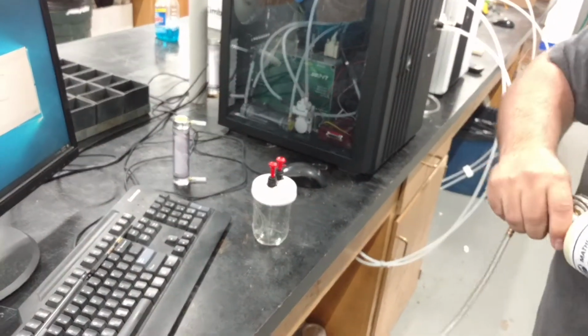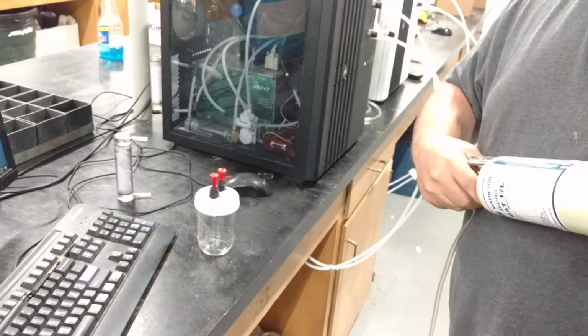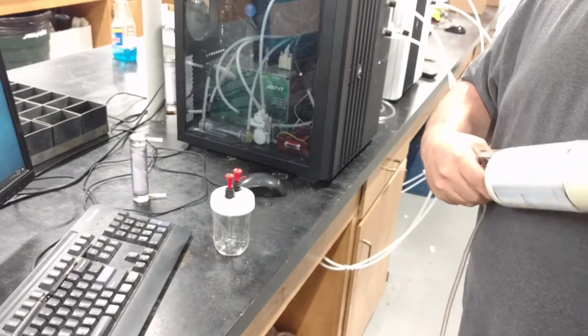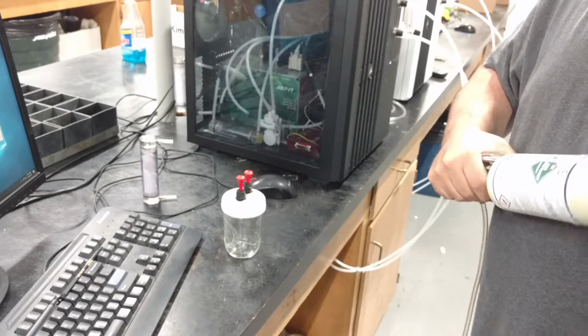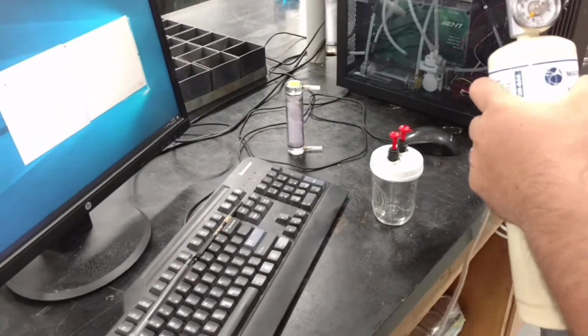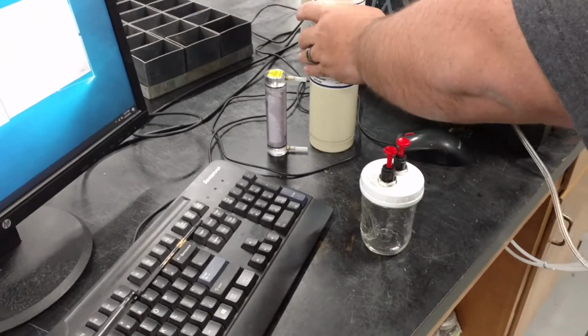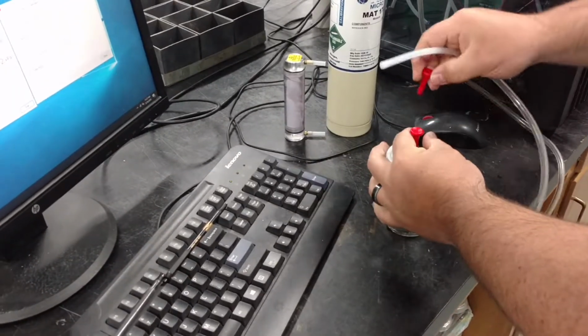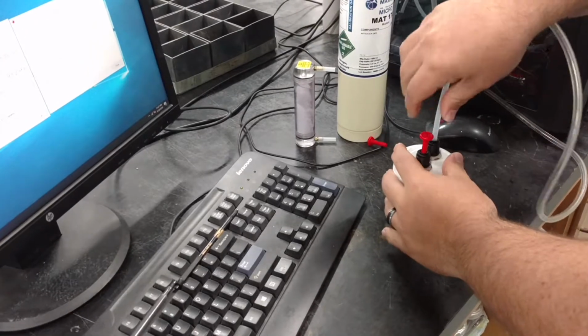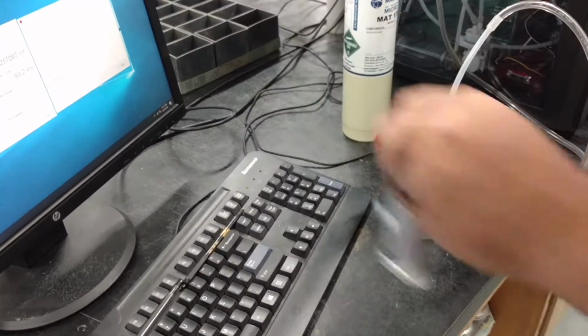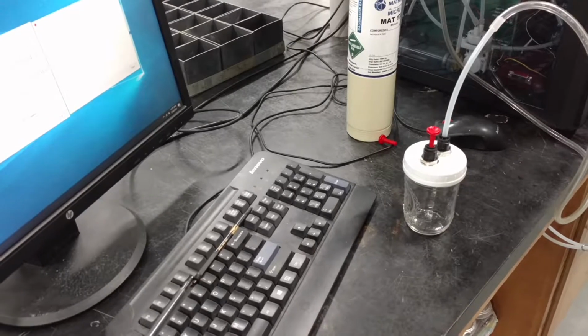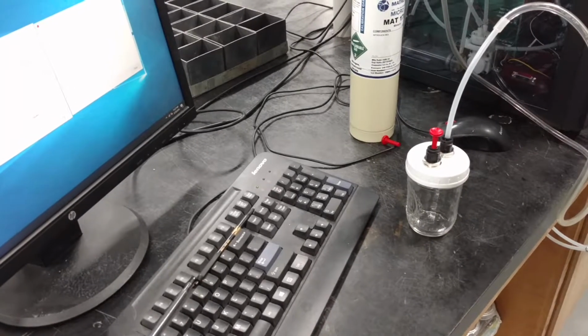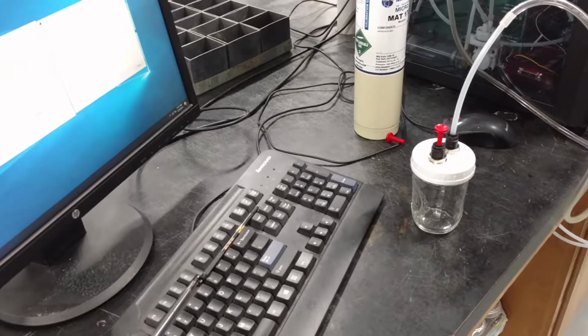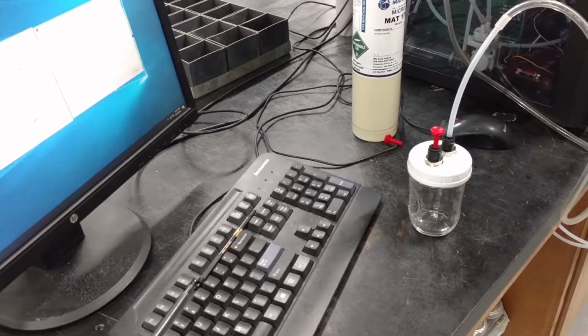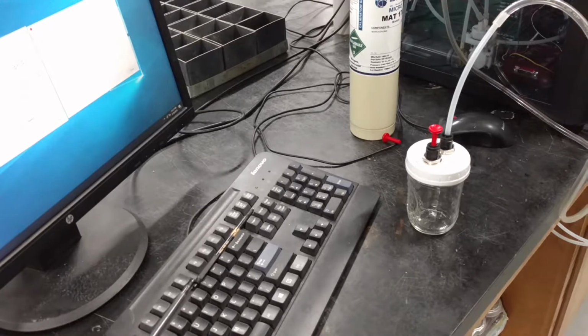We're going to start with a 0% CO2 or a nitrogen matrix gas. You'll want to connect the regulator, either supplied with your instrument or purchased separately, to the proper canister. With the regulator attached, you're going to set the flow rate to about 2 liters per minute, and attach this to one of your jars. The red plug in the second port should be loosely sitting on top to allow gas to enter the jar and exit the second port. You're going to allow the calibration gas to fill the jar for about 15 to 20 seconds before moving on to the next step.